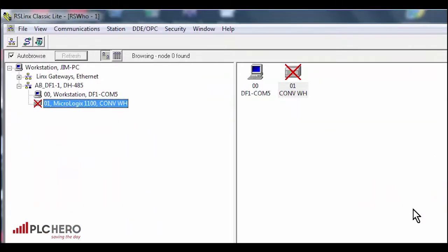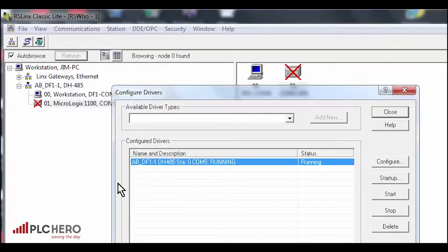And go to your RSLinx. The screen we're now looking at shows that there is an X on the PLC. Whenever you see a red X, it indicates that at one time we had communication established, but it's no longer true.